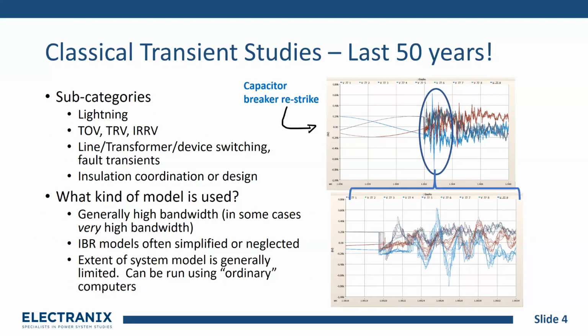In the 1970s, people were designing the first algorithms and the first commercial and non-commercial tools that were able to look at transients to a degree that they weren't in the past. So some subcategories in what I would call classical studies would be looking at effects of lightning, of transient overvoltage or transient recovery voltage, switching of lines, faults, transients to evaluate arrestor energies, and doing insulation coordination.